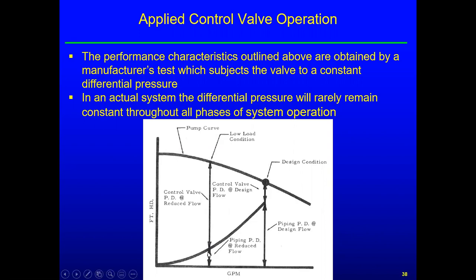At any rate, then you have the long arrow that gets you up to the pump curve, because that's where you have to operate, is on the pump curve. And so we see that, my goodness, that control valve has a huge pressure drop across it. And that represents lost energy, that's pump energy that's just being dropped in order to reduce the flow rate. That's why a variable speed situation is much more efficient.